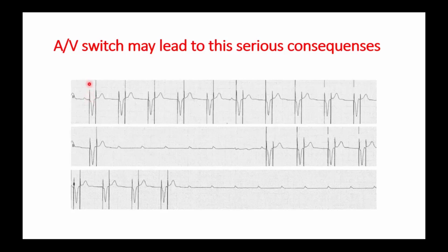This is for the device: atrial based, V sensing, A pacing, V sensing. But A pacing, because the atrial lead is in the ventricular port, it is delivering the impulse into the ventricle. The ventricular lead is in the atrial port, so there is no impulse reaching the atrial lead. It did not sense the atrium, so it paces, and when it paces, it gives the ventricular QRS complex. And there is no retrograde conduction here.